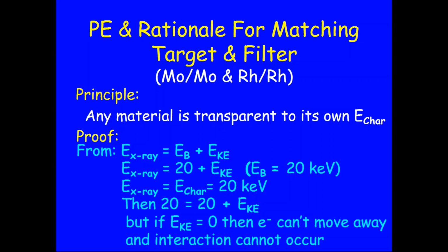You know, it was a Bremsstrahlung production of energy. So you had low energies, you had high energies. The low energies produce dose. The high energies degrade image quality, degrade subject contrast. So we were looking for a way of eliminating those low energies and high energies, but allowing the good radiation, the 20 keV optimal energy radiation to get through.